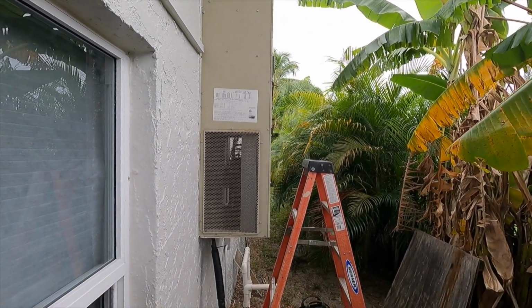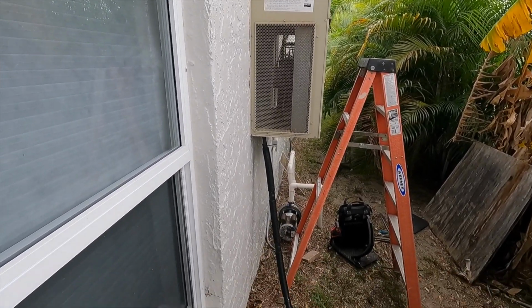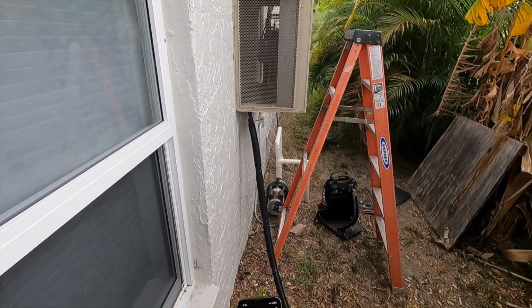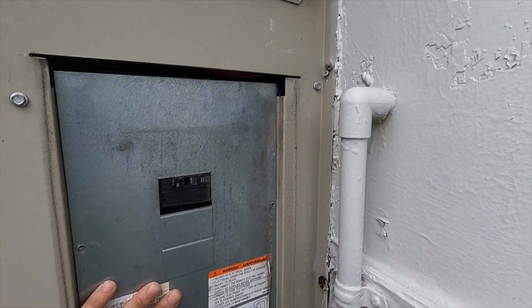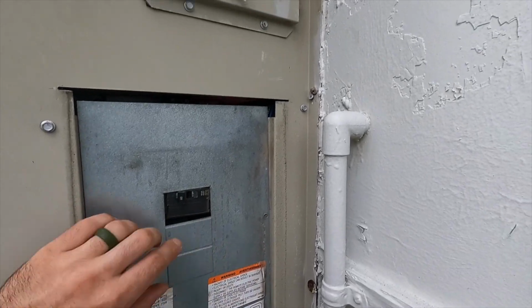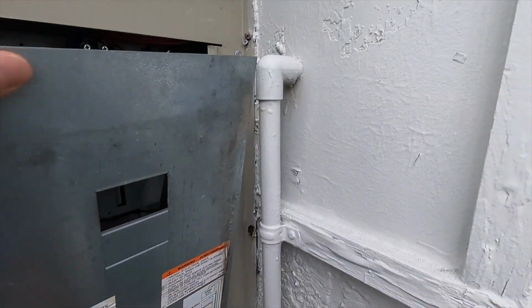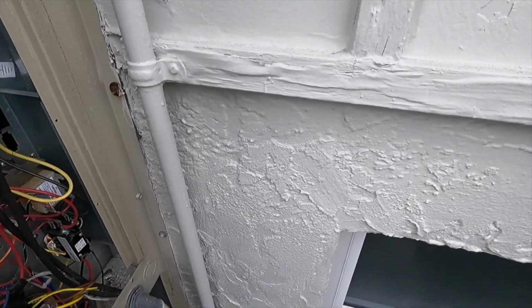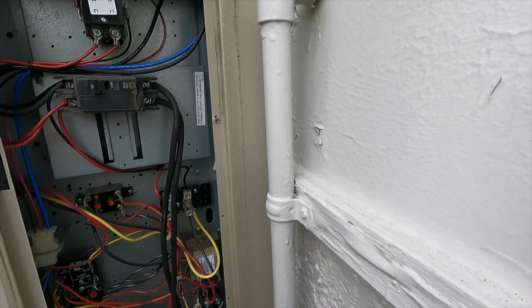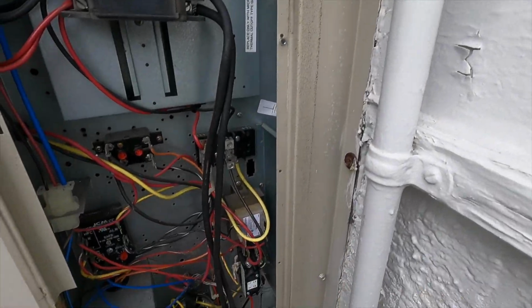All right, I'm going to go ahead and pop some more panels for the electrical now that we've checked the refrigeration, and we'll check back in. All right, so off the bat here I can see we got a 60 amp breaker. That's going to indicate to me that we got a 60 amp breaker for the total unit. I'm going to take a wild guess that we got maybe a 5 kilowatt heater in this thing.